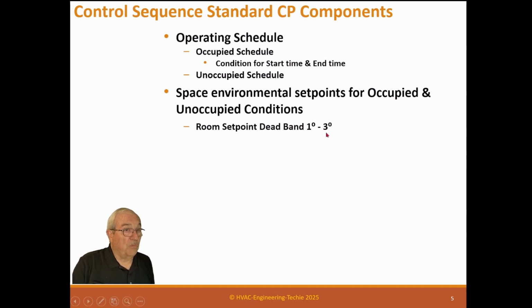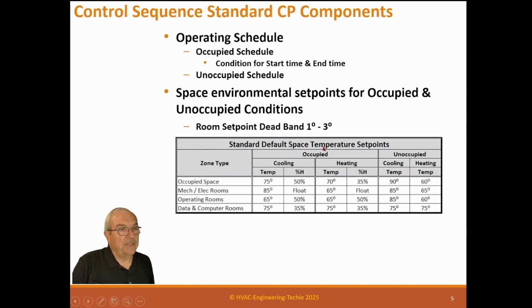So 1 to 2 degrees is what I would prefer, to keep the cooling and heating bands apart, but not 4 degrees. These are the standard temperatures out of Guideline 36. So occupied spaces for cooling are 75 degrees, 50% relative humidity. Heating is 70 degrees, 35% relative humidity.